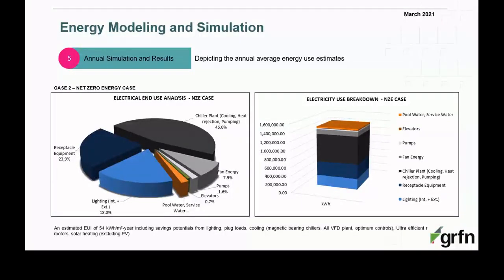Most of the savings are probably coming from the chiller plant, because we have a much higher efficiency water-cooled magnetic bearing chiller. It's an all-VFD plant, so there are VFDs on the condenser pumps, on the cooling tower, and on the primary pumps, and we use an optimum control. We did an R&D project with one of the leading district cooling companies, and we came up with an algorithm to run the different components of a chiller plant in an optimum way based on the outdoor conditions. This is what we've used in this simulation to get the energy consumption of the chiller plant. As you can see, the consumption is almost half. The EUI dropped from 118 to 54, so it's even less than half.